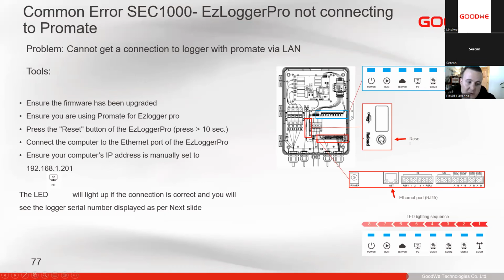We press and hold this reset button for approximately 10 seconds. When you let go, you'll see the LEDs will go from right to left. We need to see the LEDs cycle from right to left. If we don't see that, we need to press and hold it a little bit longer, let go, and see it go from right to left. Once we've seen that right to left, then we know the device is now set to a static IP address and we can connect to it.